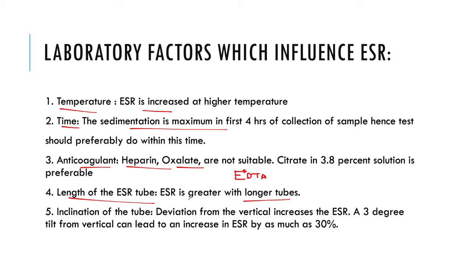And the inclination of the tube is very important because the tube should be completely in the upright position, it should not be in a tilted position. Otherwise the rate can be false. So that's why the inclination of the tube is also very important. It should be completely in the vertical position.